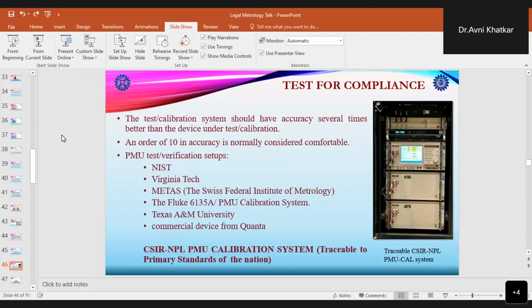However, the Fluke 6135A is a racked system, that is, it is on wheels, it can be purchased, and it can be used for testing in the field also. It is automated, and by automation and by traceability of this system, tests of PMUs requiring around 6 to 12 hours per PMU can be done. And at CSIR NPL, we have established this PMU calibration system, and it is traceable to the primary standards of the nation.